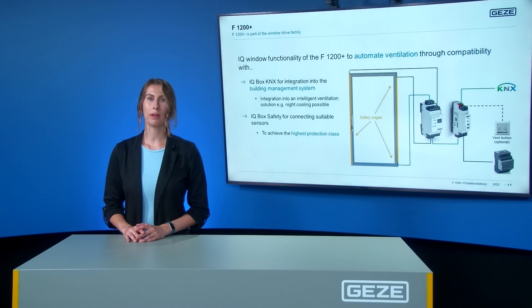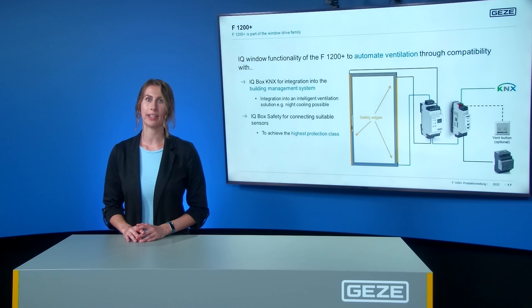Due to the maximum opening width of less than 200 mm, the F1200 Plus already fulfills Protection Class III according to the Machinery Directive. In combination with the IQ Box Safety and corresponding sensors, Protection Class IV can be realized, meaning the main and secondary closing edges are adequately protected in automatic mode. Protection Class IV is primarily required in buildings where persons requiring special protection are located.